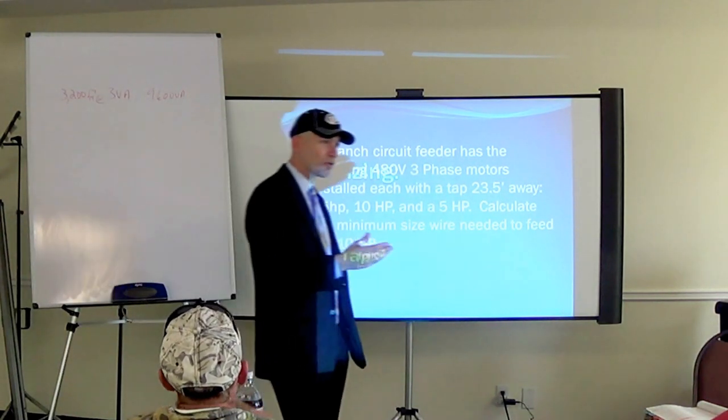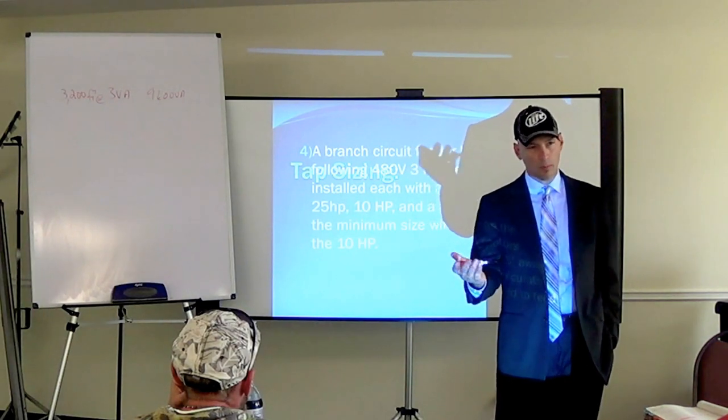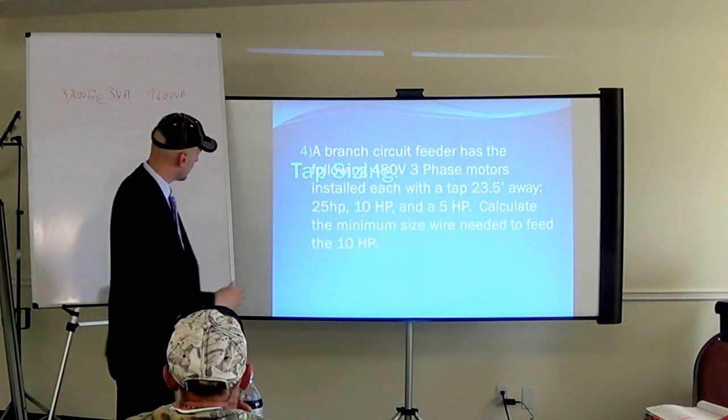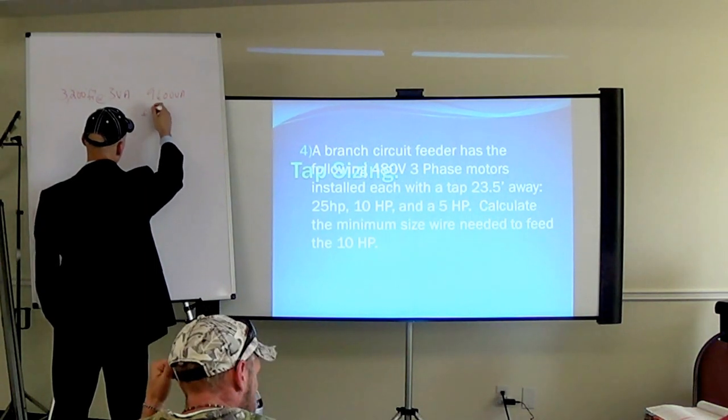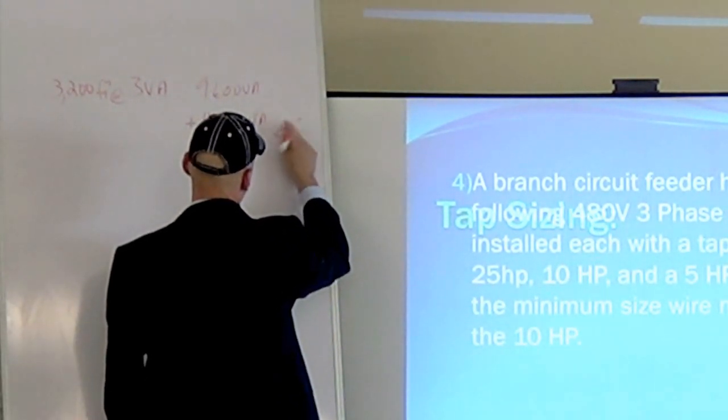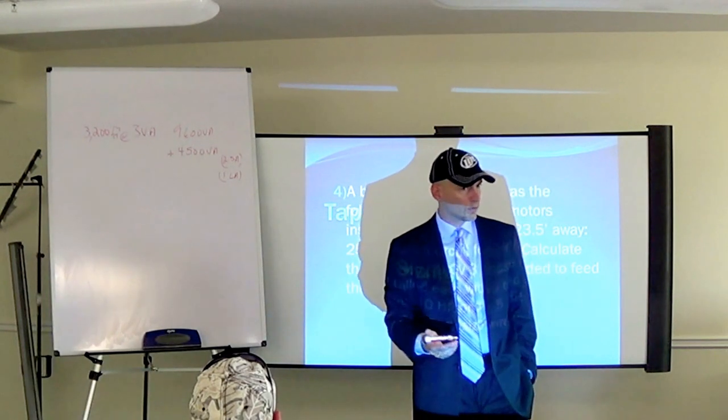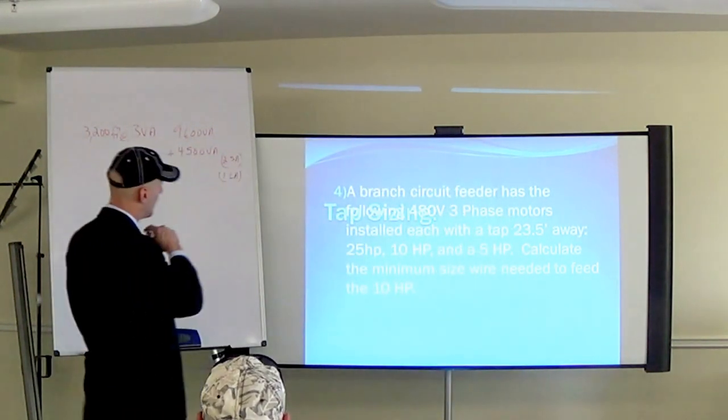The bathroom, you know, you're going to have some high amperages, so you need a high enough circuit to handle all of the load. But it's a short duration load, so we don't have to worry about the demand calculation against the service, which is a much bigger concern in the kitchen areas and the laundry areas where you've got irons and the countertop mounted cooking equipment and beyond for quite some time. So to this value here, we're going to add 4,500 VA total, and that's for the two small appliance circuits. One and two and one laundry. For you guys only, laundry circuits sometimes in multifamily dwellings may be excluded right here if you have common provisions for laundry facilities that people have access to. But that's it. In a single family, you can never take it out. It's always going to be. There's no exception in the rule for the same kind of load. In this case, we'd have to have it no matter what.